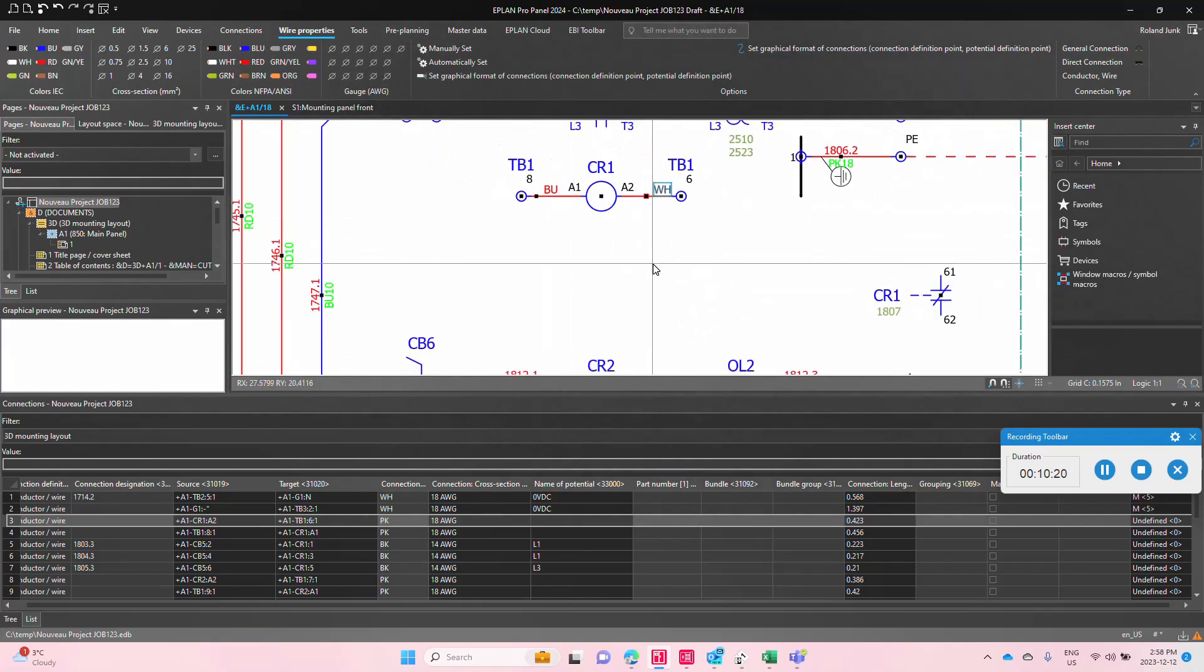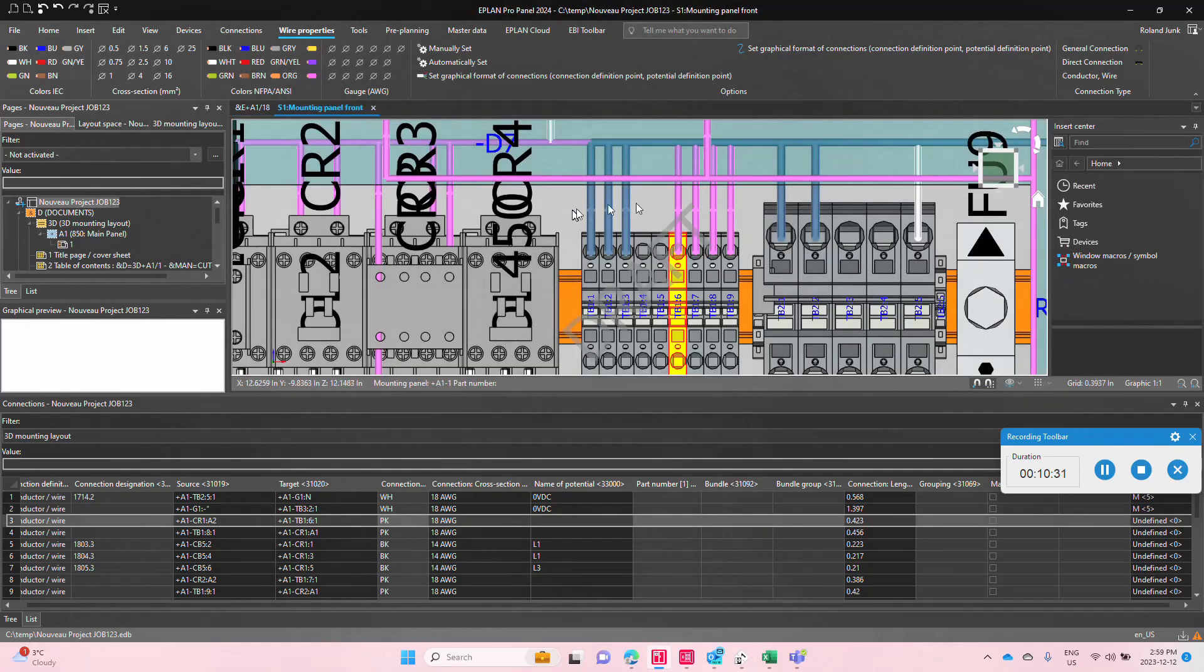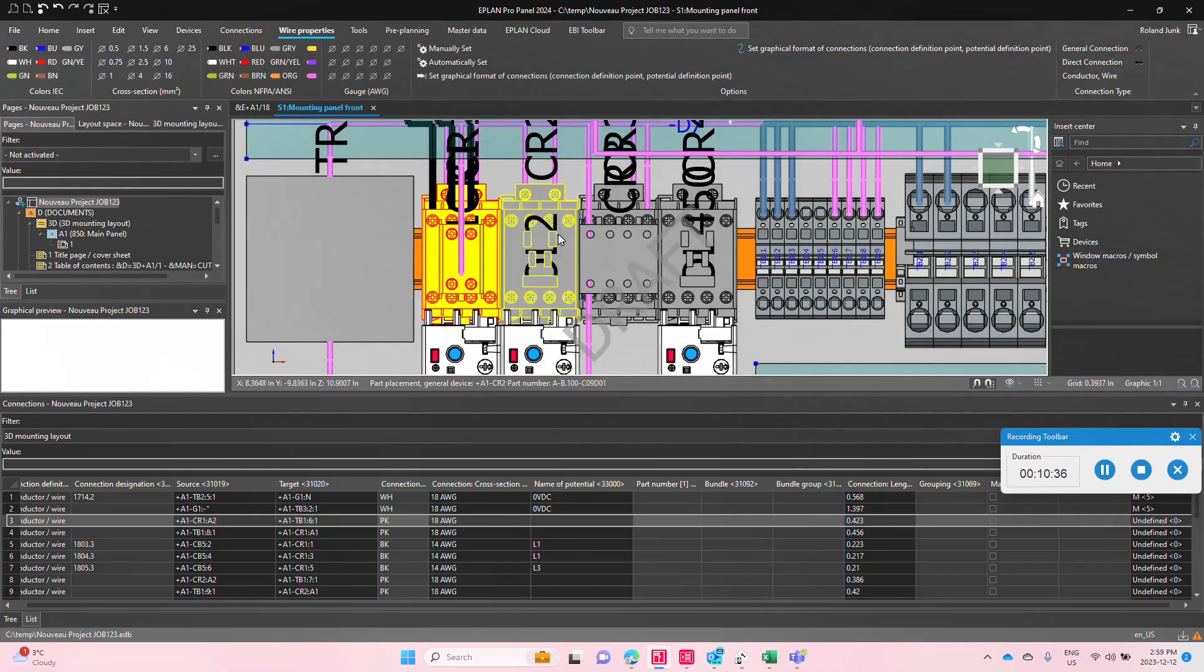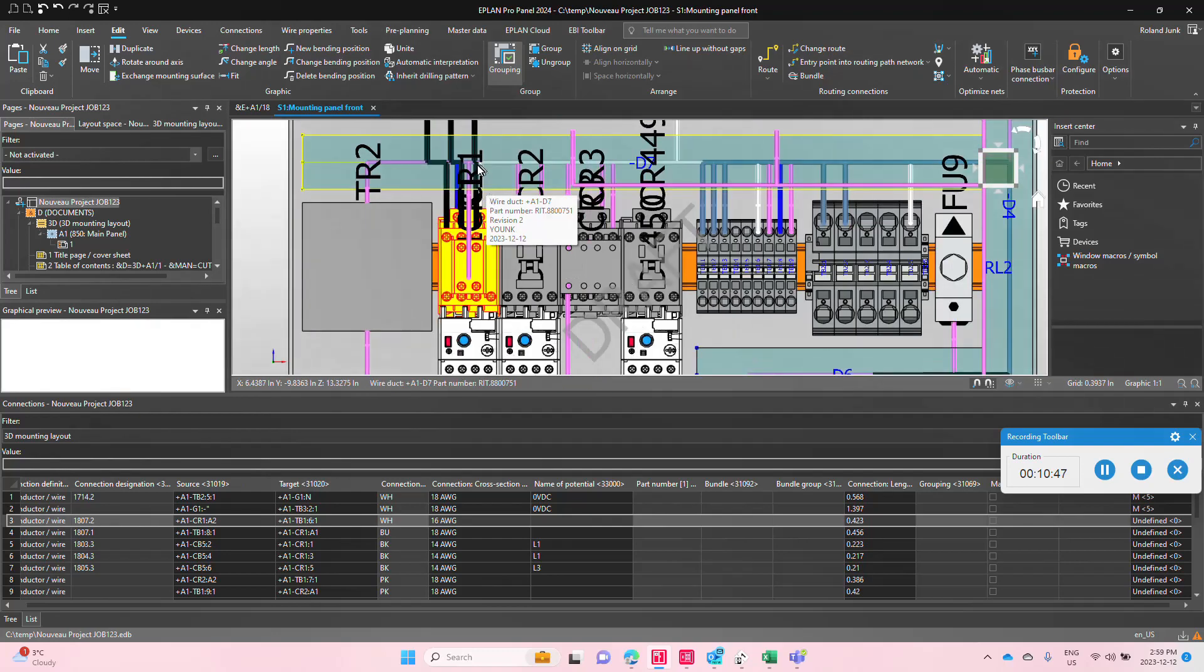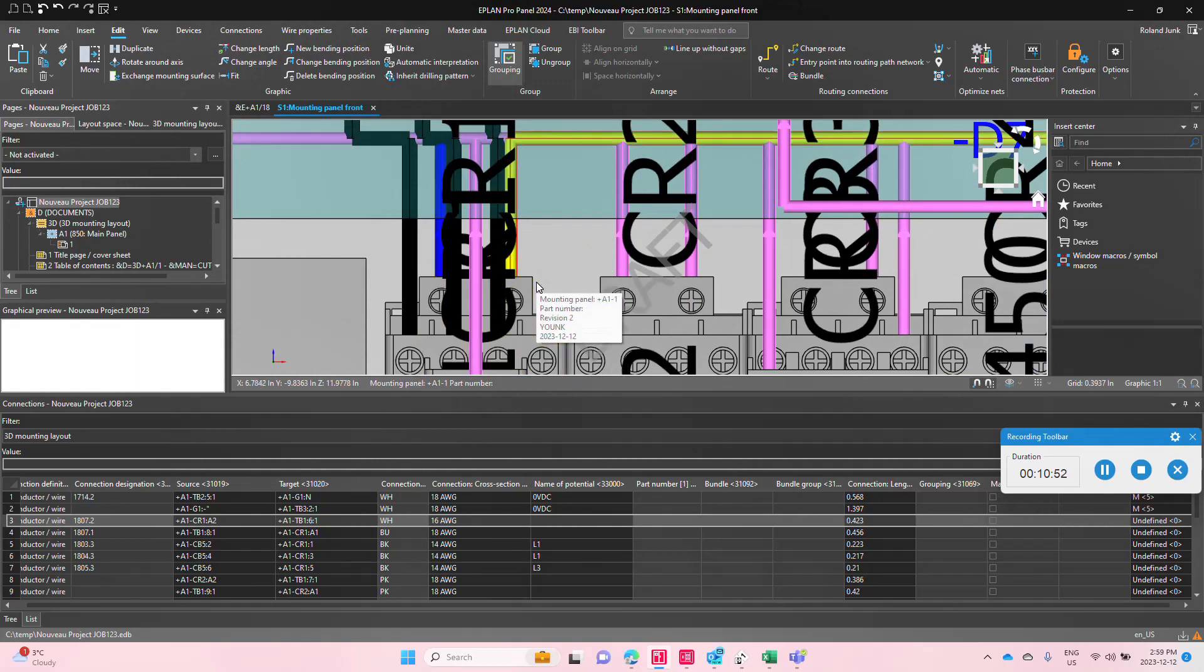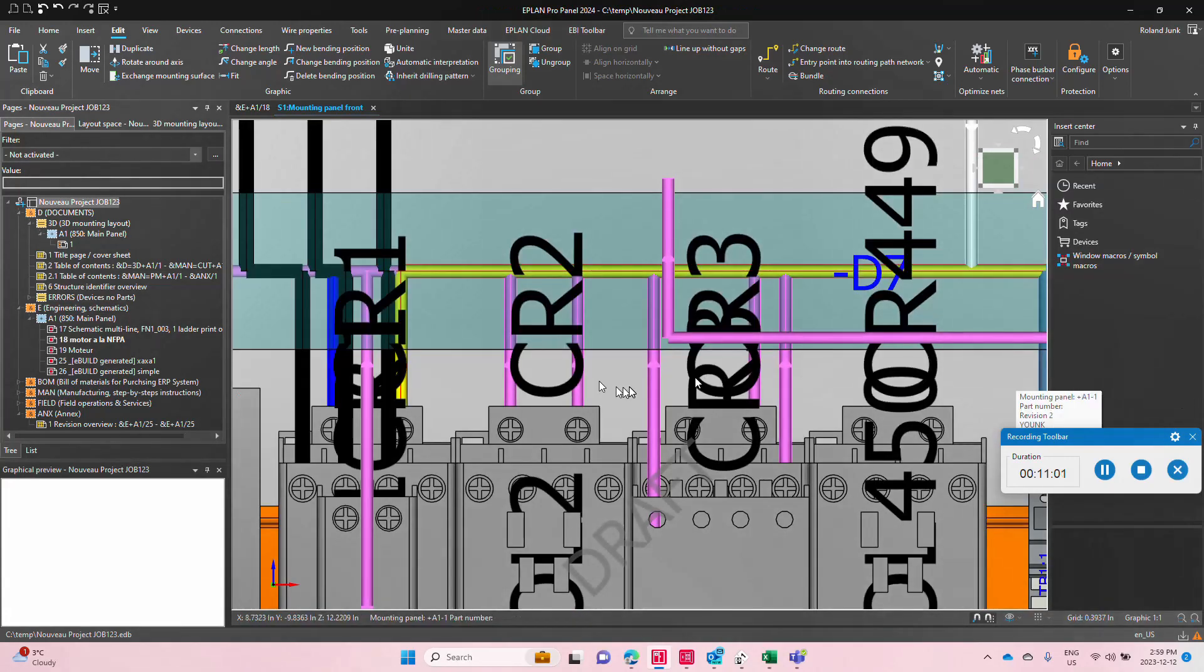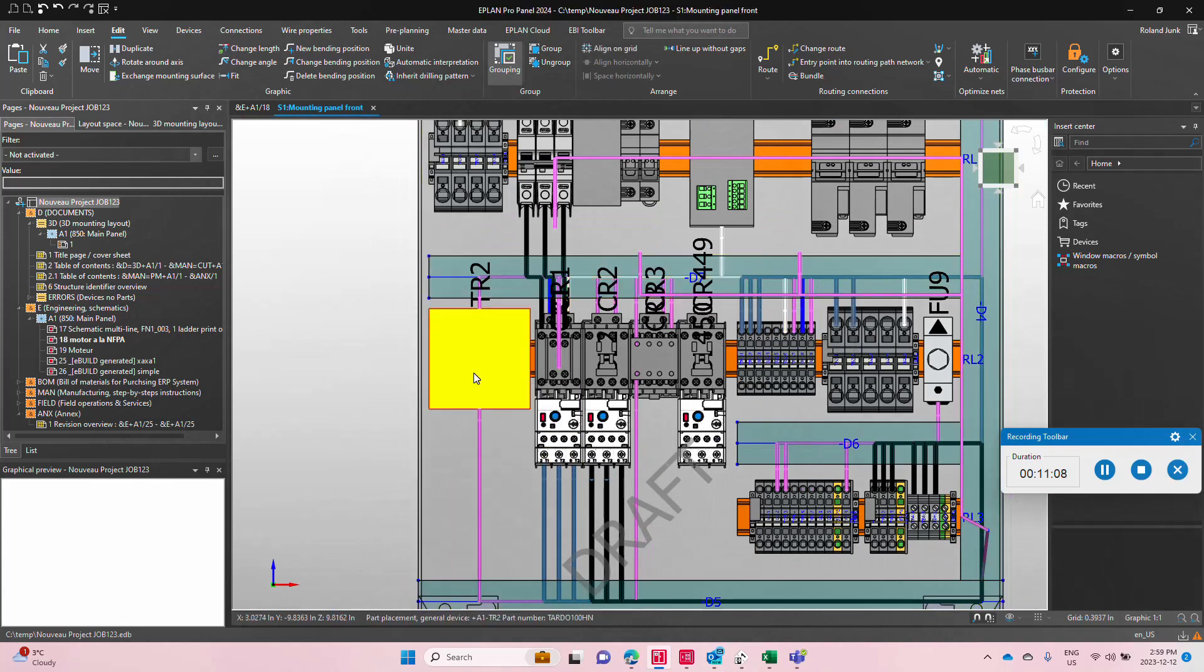What I could also do is this wire here. I have a small toolbar here where I can actually assign a white, and then here 18 gauge unfortunately is not on that. I'll make it 16 gauge. And bingo! Now this wire is and became the right color. And if I rerun, let's say we go back to here, CR1. So I can go here back into my control relay here. I can check it out. If I rerun it, in particular on the front end, you will see that the pink wires will go away. And now we have a blue and a white wire, as you can see, that actually appeared here in the background. And this is how you actually can fine-tune all of these wires to make sure that you have the right color if the color is not assigned through the potential.